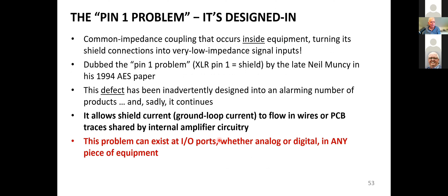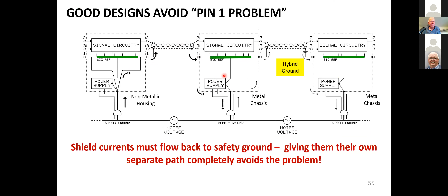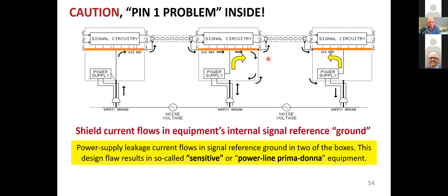So the pin 1 problem is pretty straightforward. This is how it works. It's what happens when you land pin 1 of an XLR connector on signal circuitry, like a circuit board in a part, instead of landing it to the chassis, and this is what AES 48 is all about. You land pin 1 directly on the chassis. It's supposed to be an RF shield extension so that the cable shield becomes part of the box and you leave the signal circuitry alone. Otherwise, when some of the ground currents start flowing in the shield connection up here, the voltage drops in the traces on the board will make the output have a hum. And that's called the pin 1 problem.